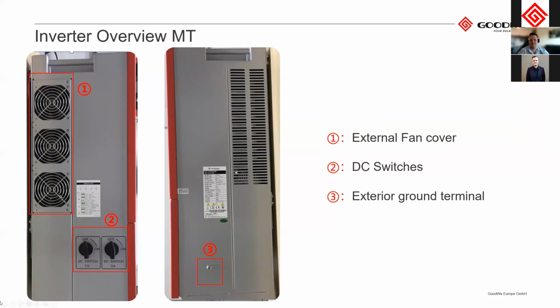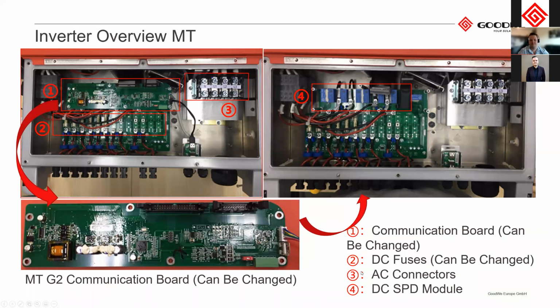At the bottom we'll see the DC switches at number 2. That's a DC switch per 2 MPPTs. And then on the opposite side, where the serial number of the device is, you'll see the grounding terminal. Here's just a look. These are slightly older pictures of the MT internal. This is the service hatch, which you open to work on the device.